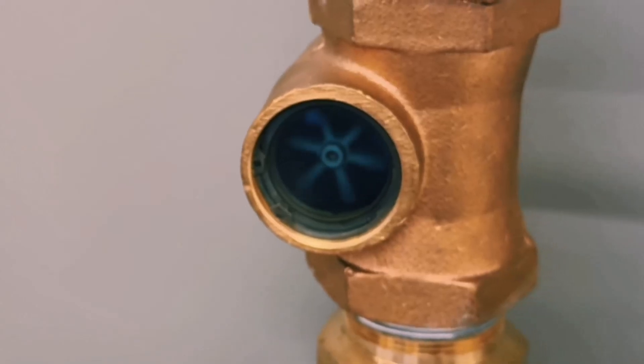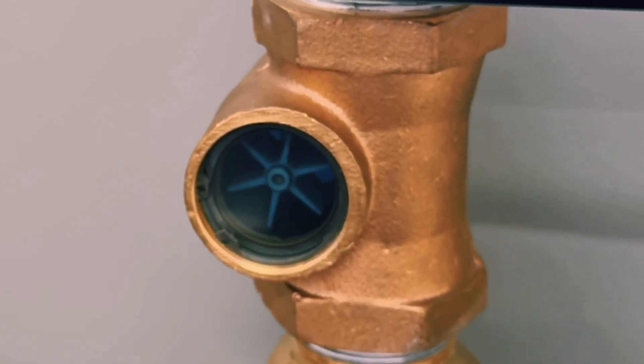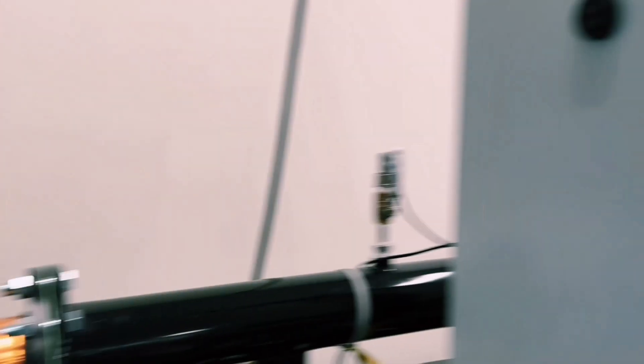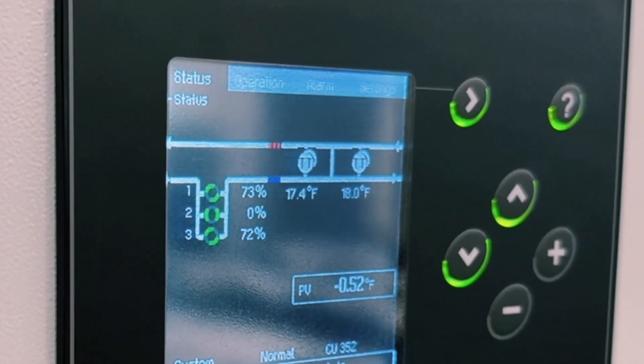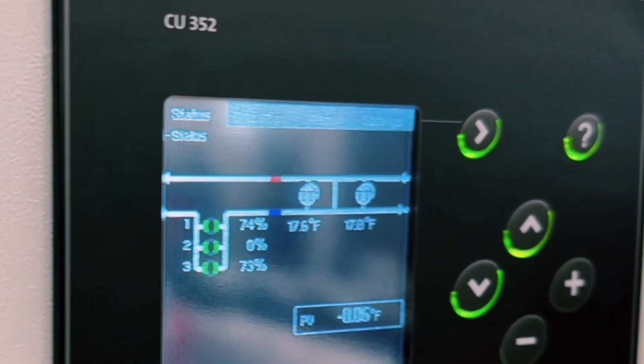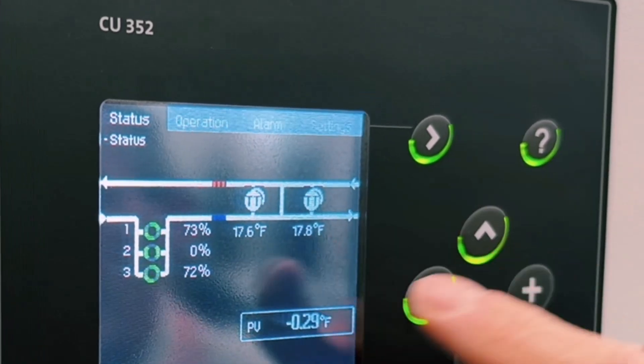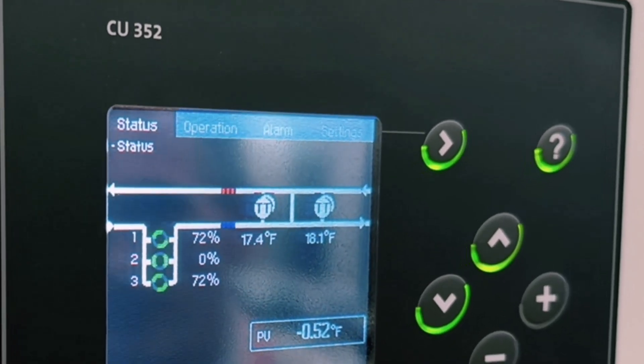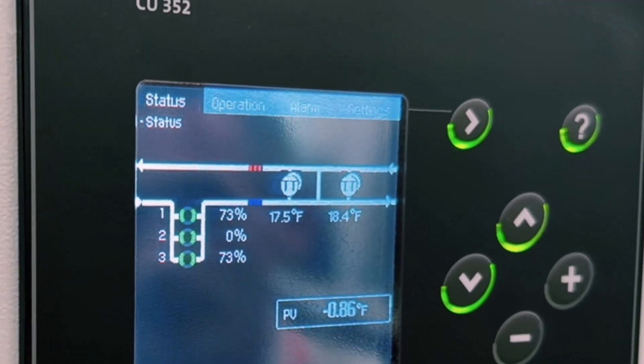You can hear the primary pump skid ramping down, and the flow through the decoupler has stopped. Looking at the controller, our flow was sufficient to need two pumps. We talked earlier about efficiency based pump sequencing — we're running two pumps at equal speed, both at 72%. That's more efficient than running one at 100% and the other at 20% or 40%.